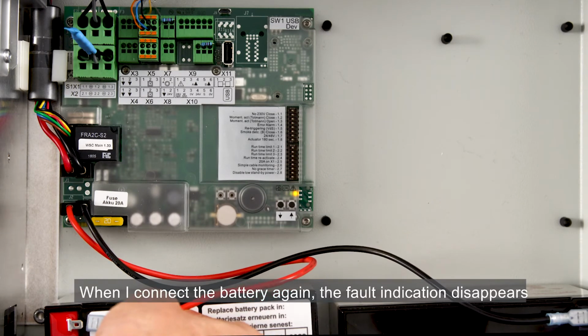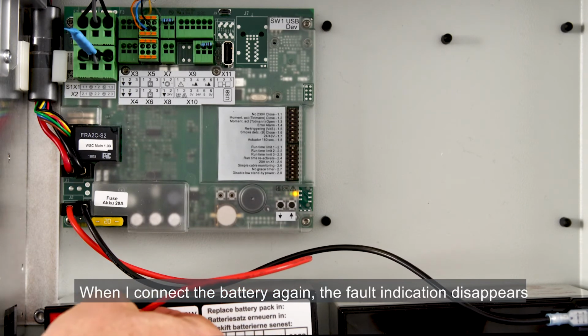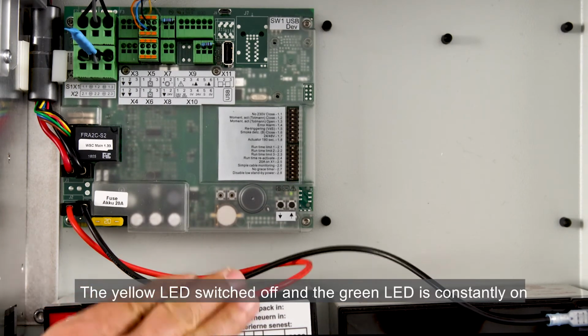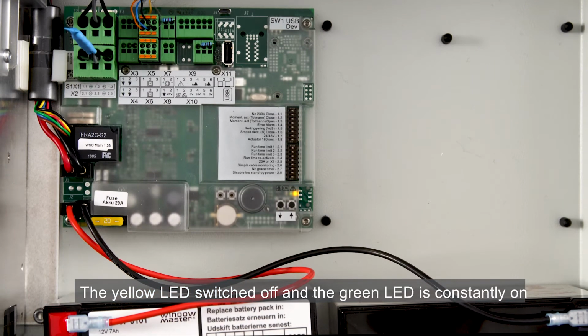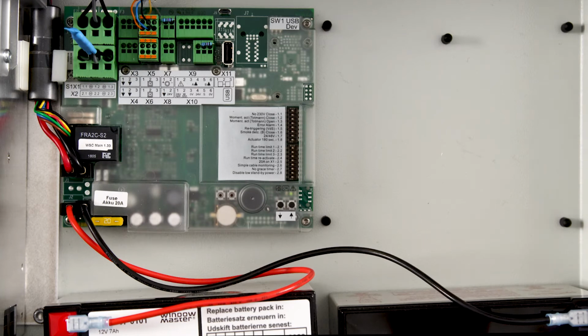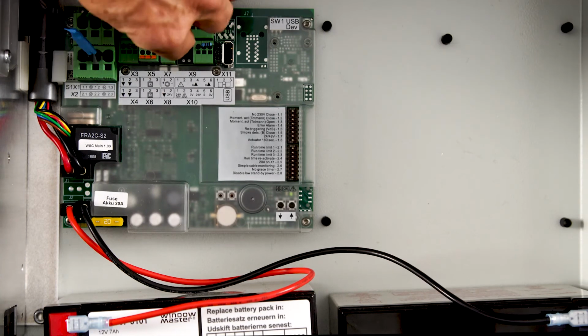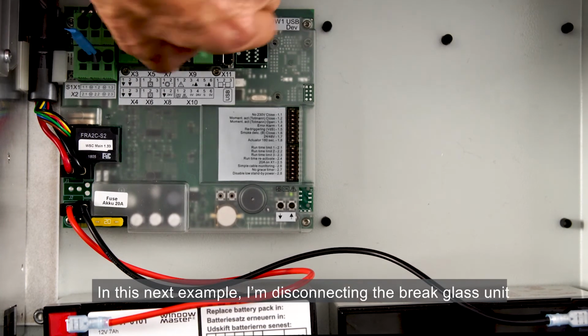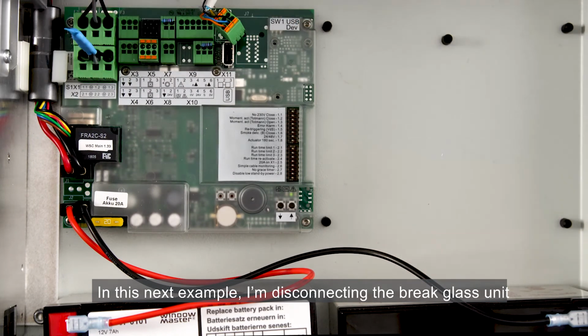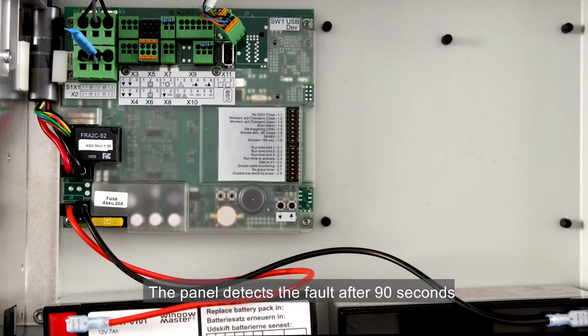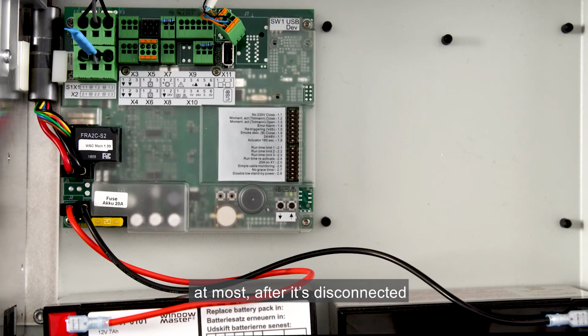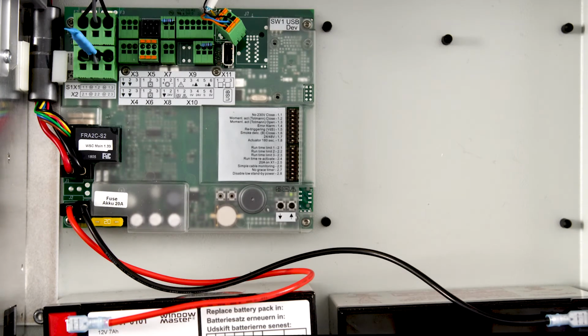When I connect the battery again, the fault indication disappears. The yellow LED switched off and the green LED is constantly on. In this next example, I'm disconnecting the break glass unit. The panel detects the fault after 90 seconds, at most after it's disconnected.